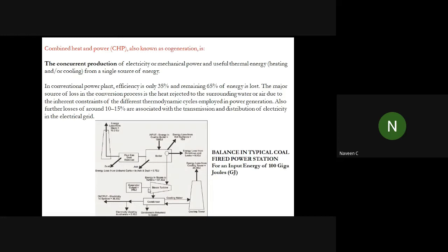The condenser-based steam turbine process is a traditional process. You are expanding the steam in the condenser to bring the vapor back to its water state. So the phase change happens in the condenser. Once the phase change happens, the water will be pumped to the cooling tower. You will have a motor here, and it will pump the water to the highest height. From there, the water will form drizzles or water droplets, and it will fall from top to bottom.